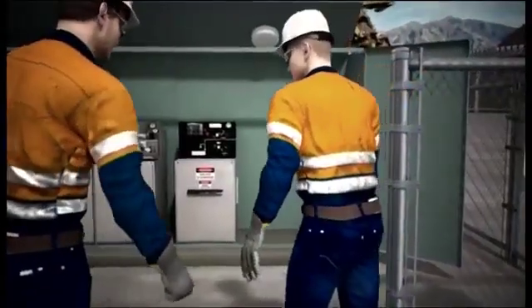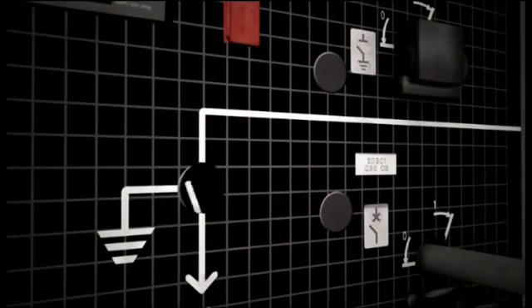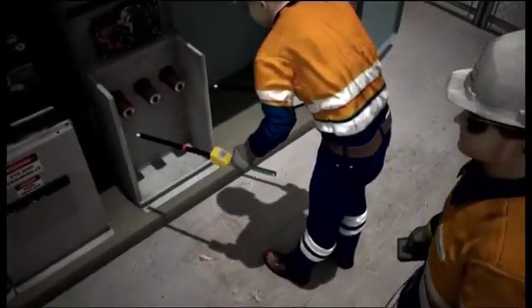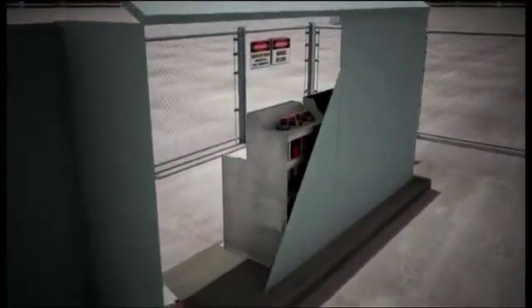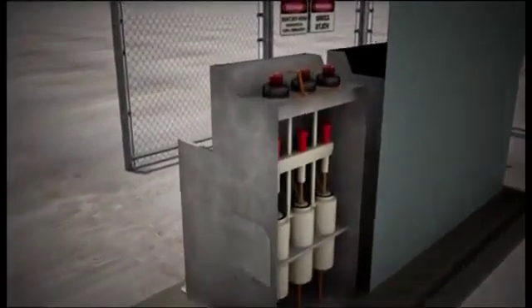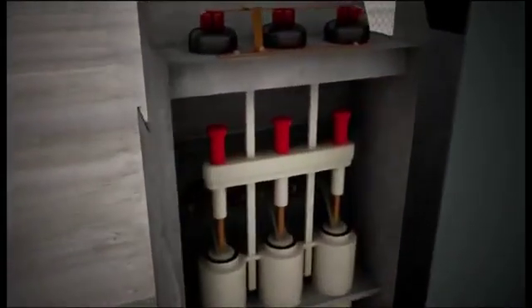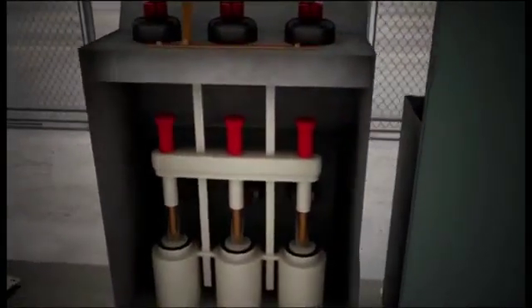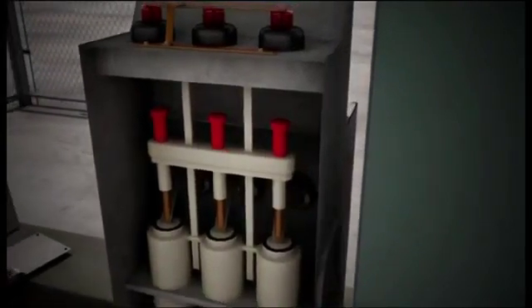Both Dave and Andrew are engulfed and both receive serious burns to their hands and face. But how did this happen? Dave was convinced that he de-energized the unit when he turned the crank handle to open, and Andrew had tested it for dead just minutes before. If we go back and view the high voltage unit from the inside, we can see exactly what went wrong and what contributed to this accident occurring.